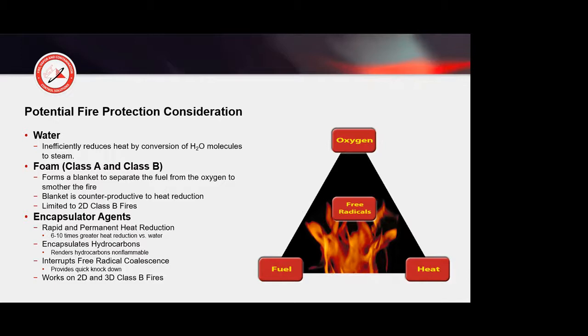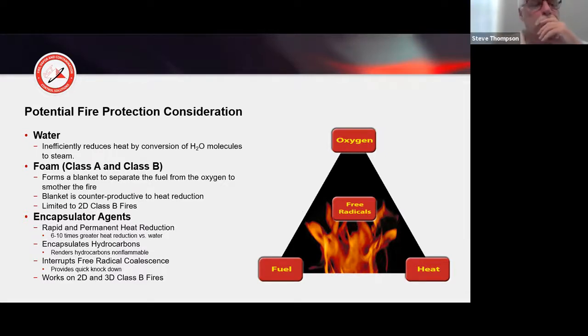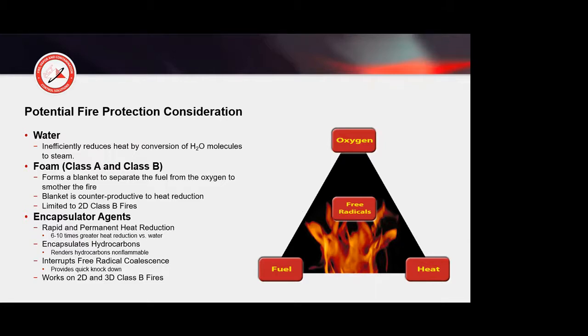If you have a pump seal fire, you are going to have difficulty with foam. If you have a three-dimensional transformer fire with hydraulic oil in it, you're going to have a very big difficulty putting the foam on and maintaining it on there for 30 minutes. The encapsulator agent works in a totally different principle, and we will get into those in just a moment. But these principles we work on all four legs of the fire tetrahedron.